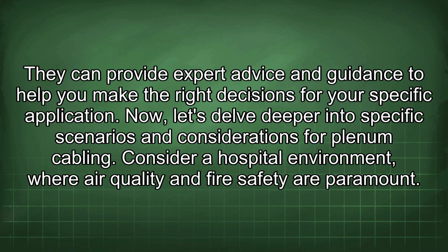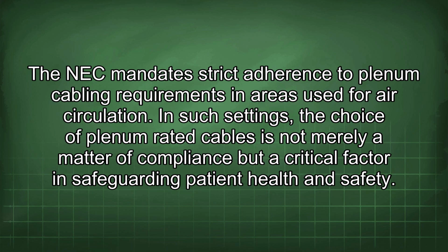Now let's delve deeper into specific scenarios and considerations for plenum cabling. Consider a hospital environment where air quality and fire safety are paramount. The NEC mandates strict adherence to plenum cabling requirements in areas used for air circulation. In such settings, the choice of plenum-rated cables is not merely a matter of compliance but a critical factor in safeguarding patient health and safety.